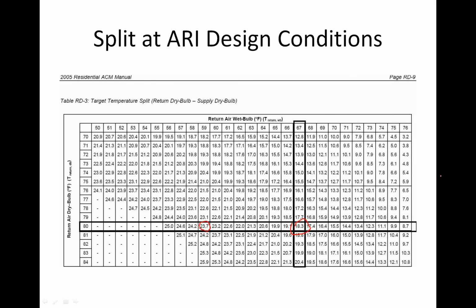As the humidity goes up, you can see here, if we went up to the far end, if we got up to a 76-degree wet bulb, we might have an 8.7-degree drop across the evaporator coil. And you go, holy cow, that thing can't be working right. Well, it's working exactly like it should, because the humidity is so high that all the energy in the system is going to convert that water vapor in the air into water.